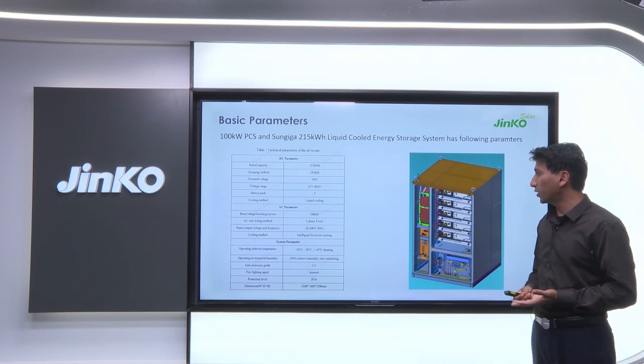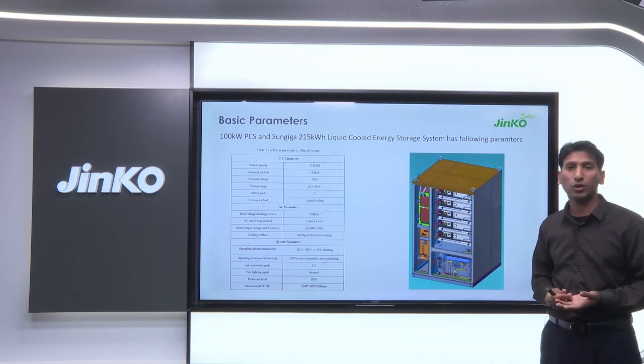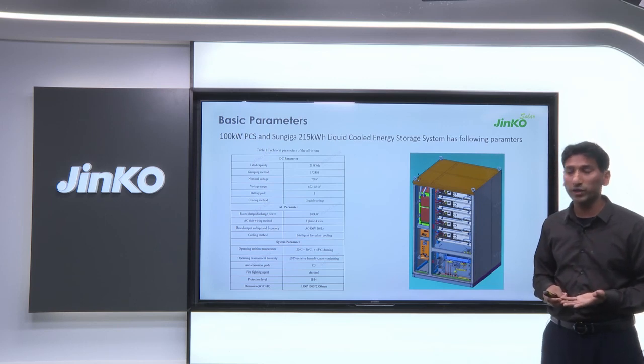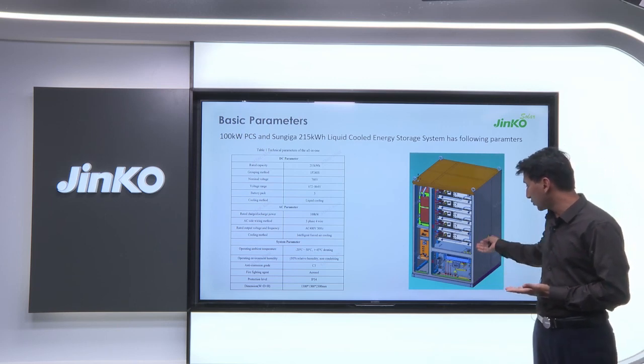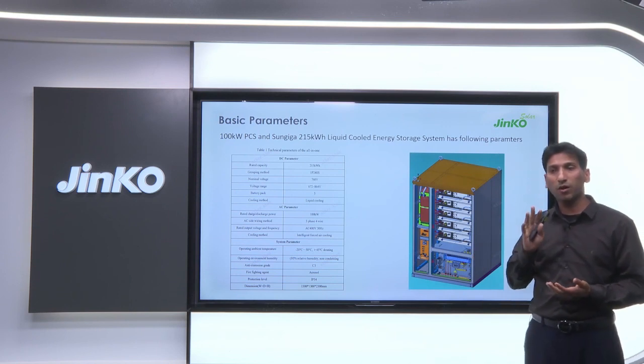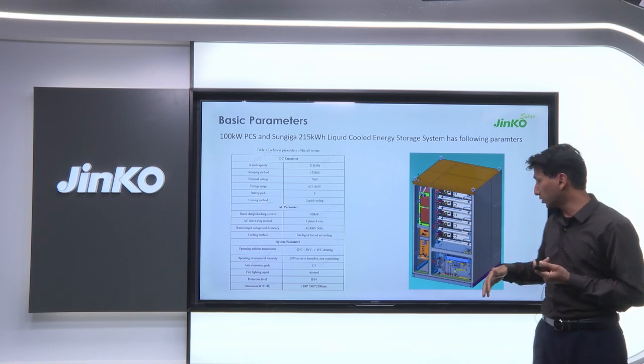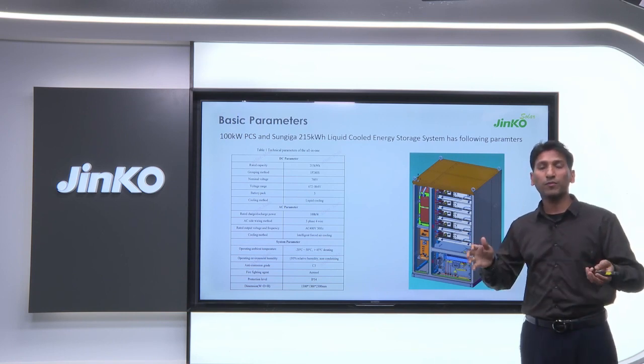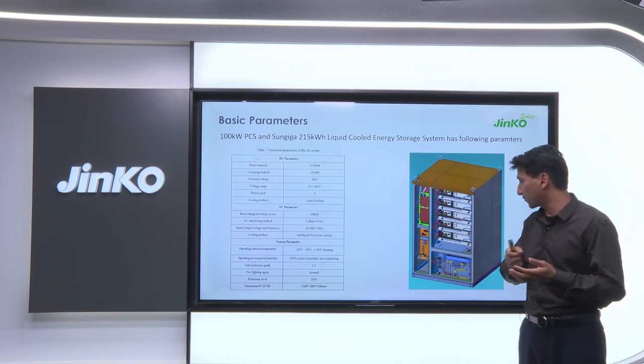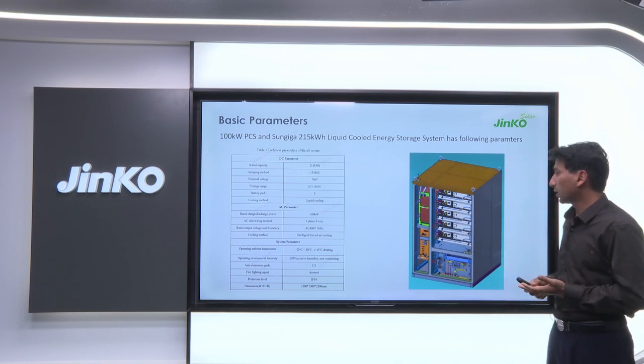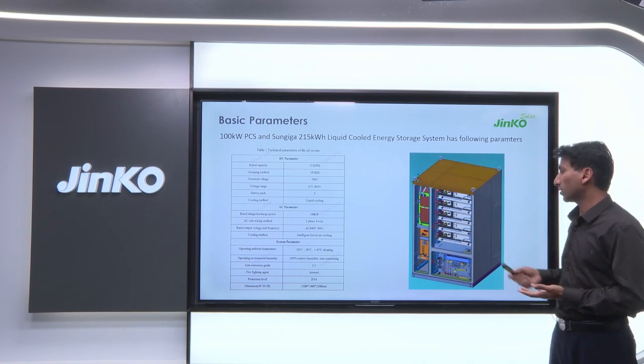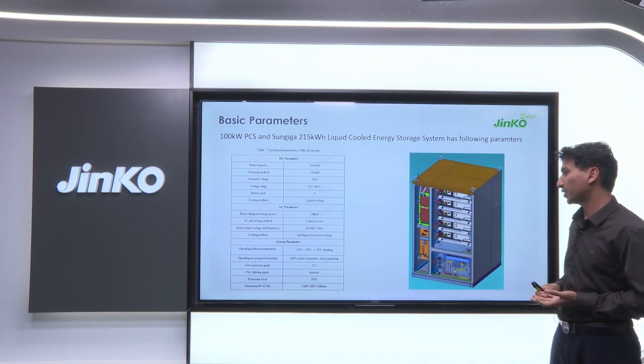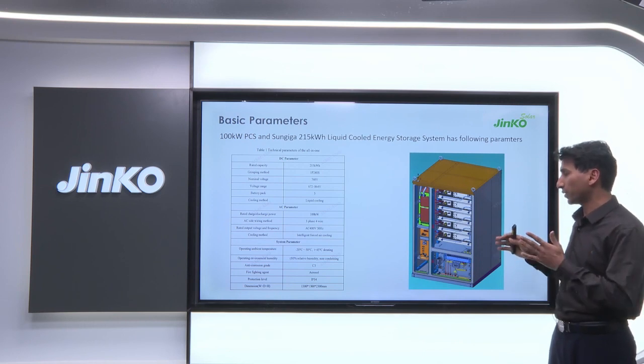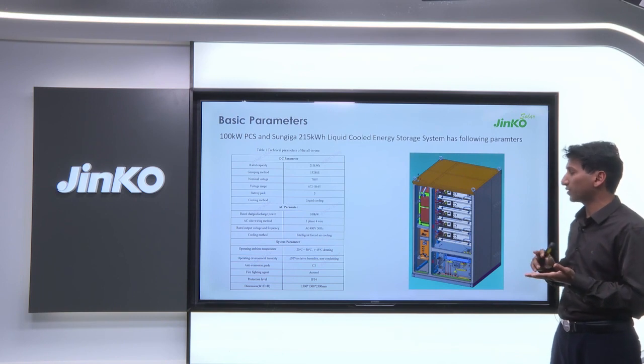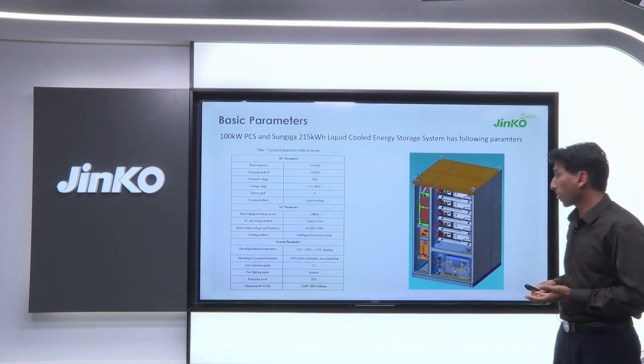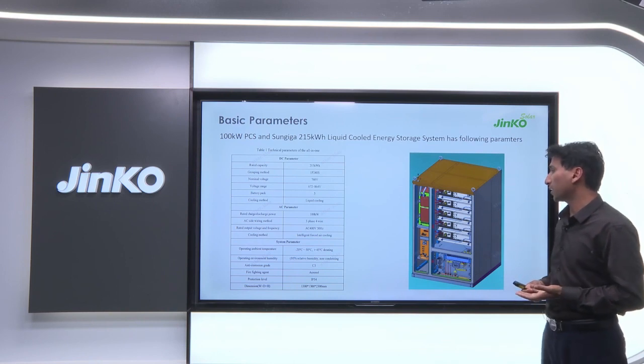But in the lower part, the ACS PCS part, we do not use liquid cooling. It uses forced air cooling. On the front, you will see 3 or 4 fans, and on the back of the cabinet there will be 2 more big fans which exhaust all the air from the inside of the cabinet. System parameters: the operating temperature for this cabinet is -20 to 50 degrees centigrade, but these are extreme values. We have to keep it between the most favorable values, 10 to 30 degrees centigrade. And the container is made of metal.